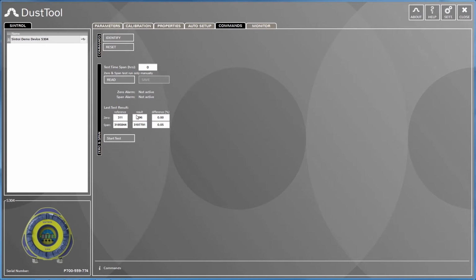On the lower part, we can read the last test results. So the 0 had a difference of close to 0% and the span of about 0.05%. If we key in, let's say, 12 hours to the span check interval, it will do twice a day, every 12 hours, it will do an automatic zero and span check. Let's save that and read.